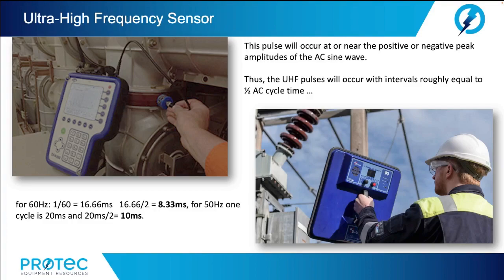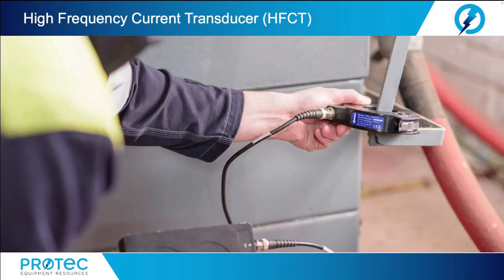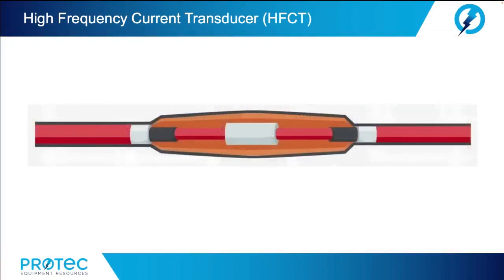Now, in some cases, such as inside a power transformer, the UHF emission may be completely shielded by sealed metal enclosures. Fortunately, the UHF signal will also induce a high-frequency current pulse onto the ground of the apparatus. The high-frequency current pulse will be detectable with a high-frequency CT, or HFCT. And that's a perfect segue into talking about the HFCT. When partial discharge occurs, there are small current pulses that are induced onto the ground shield or case ground.